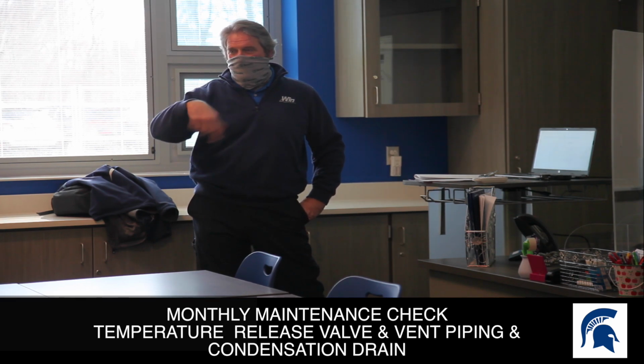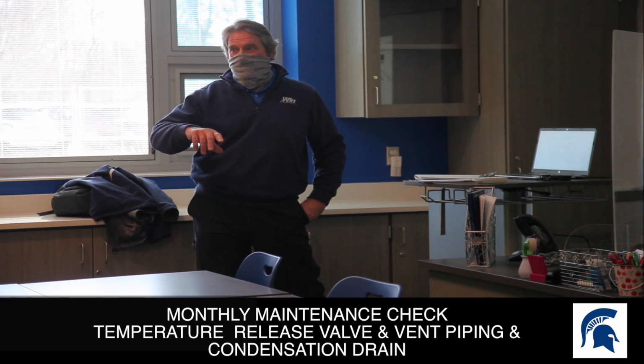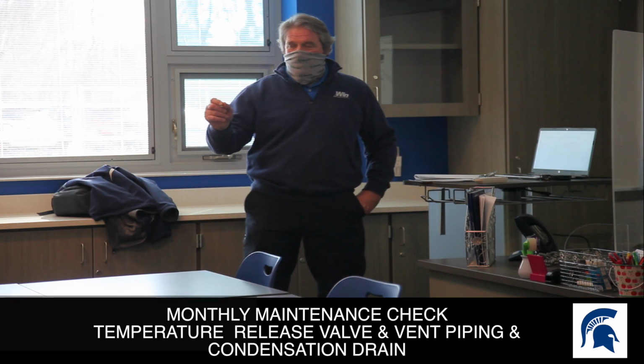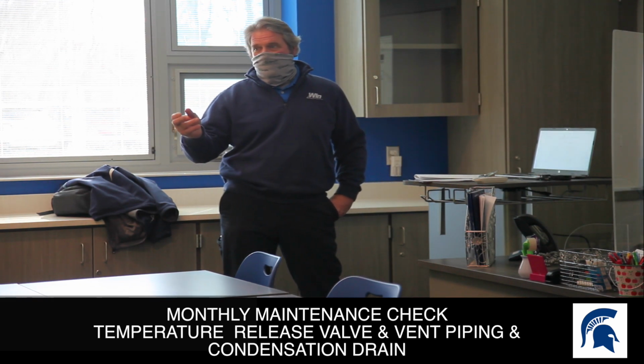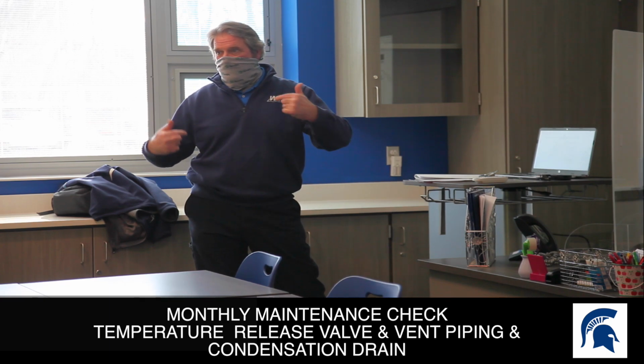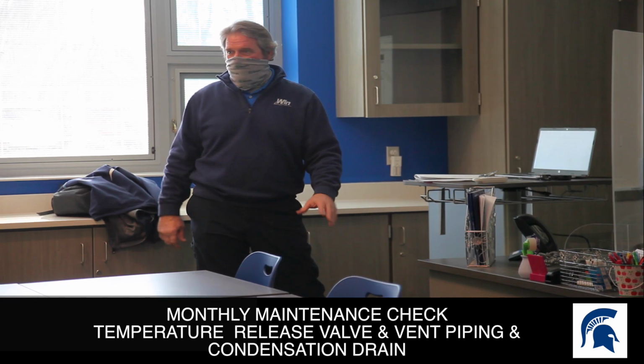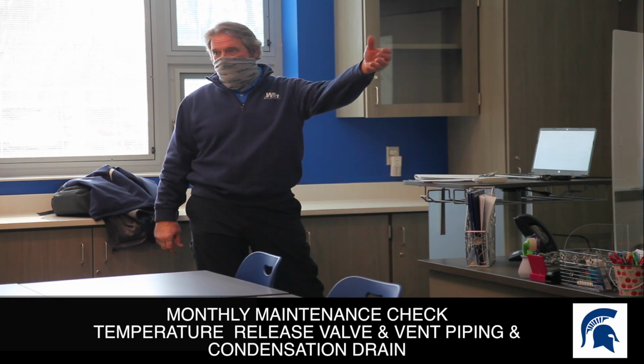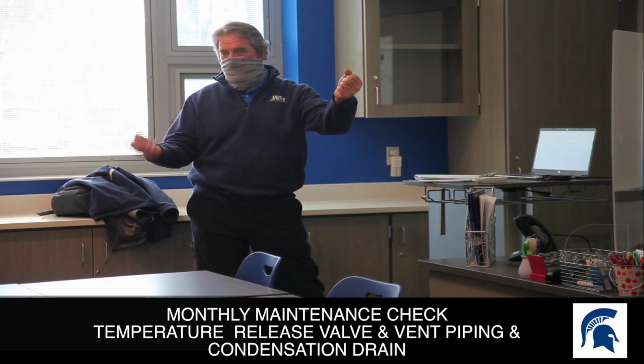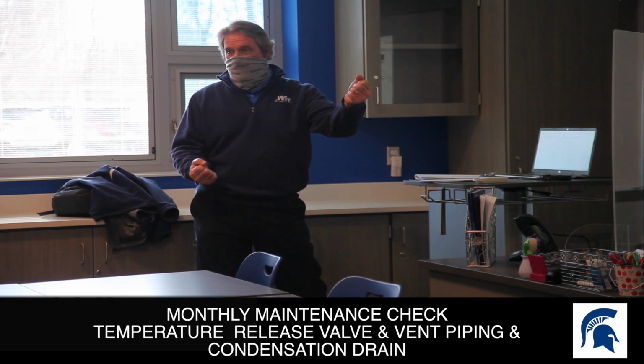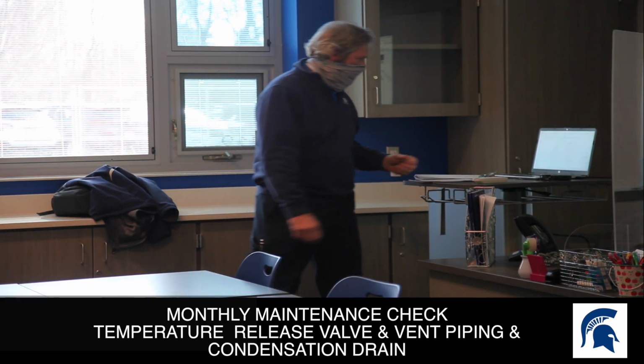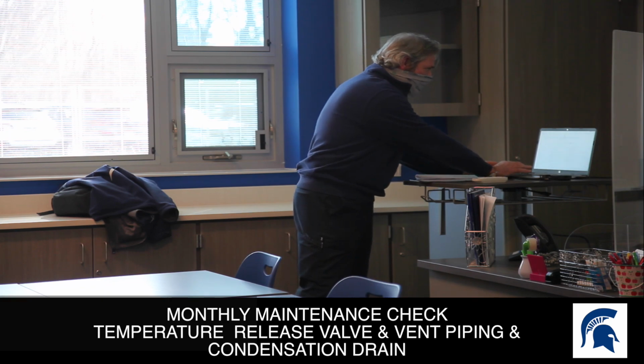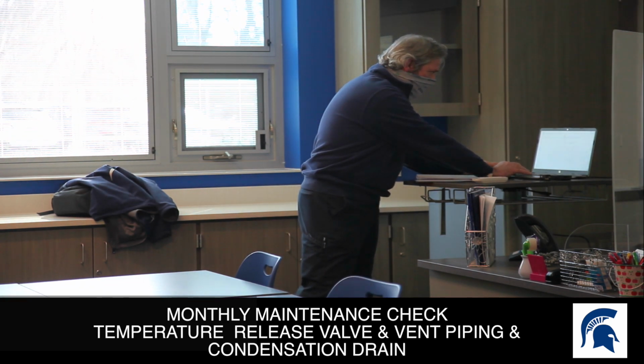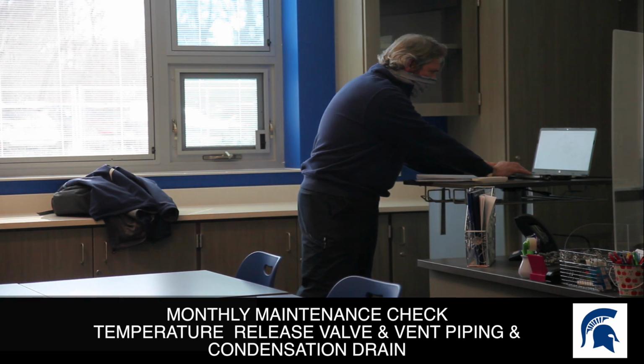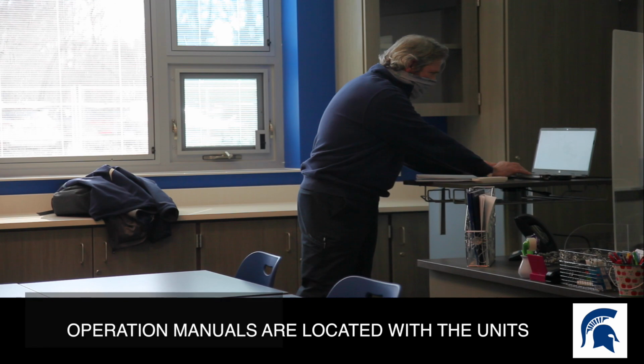It's a stainless steel heat exchanger. Okay. The only way to know when that needs flushed or serviced is when your delta T's change. If you don't have enough delta T, which is your cold coming in, you check your temperature there, and your hot water coming out should be 40. It's on the sheet in here. Once I mess it up, then I'll mess everything up. I think it's 45 degrees on this unit, or percent. It'll show you delta T's on here.